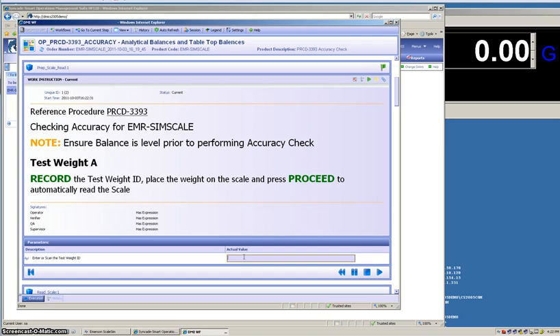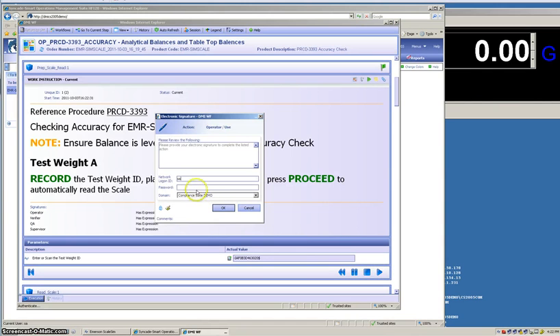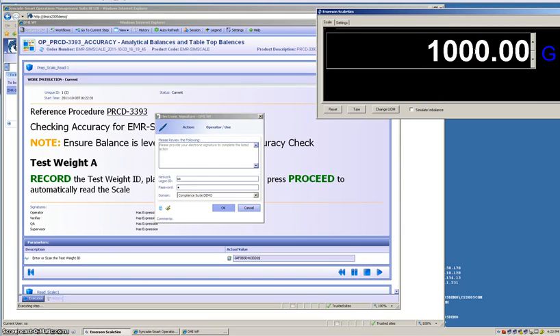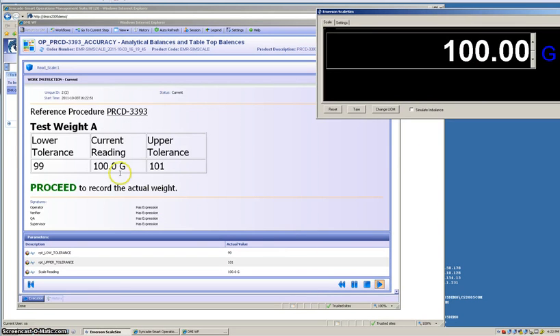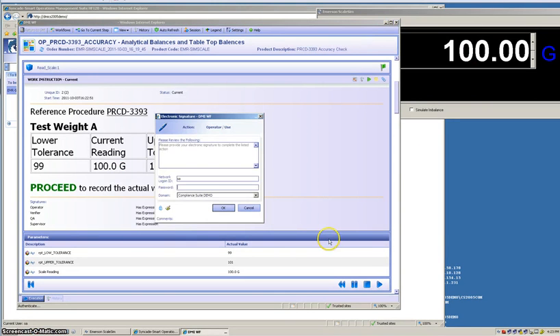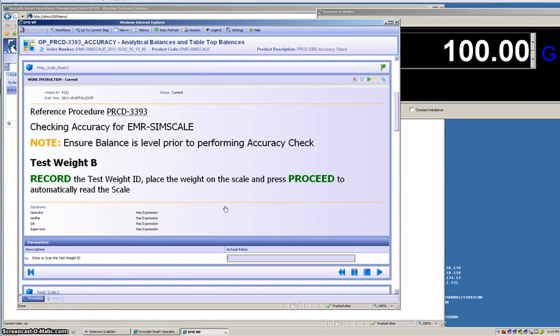Returning to our previous instruction, we'll scan the test weight again in case there was an issue with the test weight that required a change in test weights. We're going to set this balance up to the correct value. As we see now, the current reading is correct, and we're going to proceed. With test weight A accurately checked, we now proceed on to test weight B.